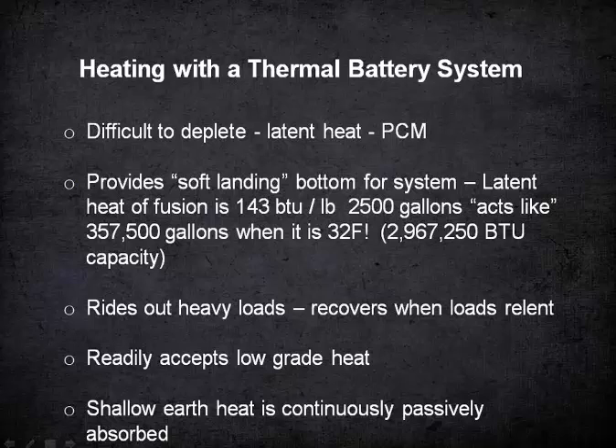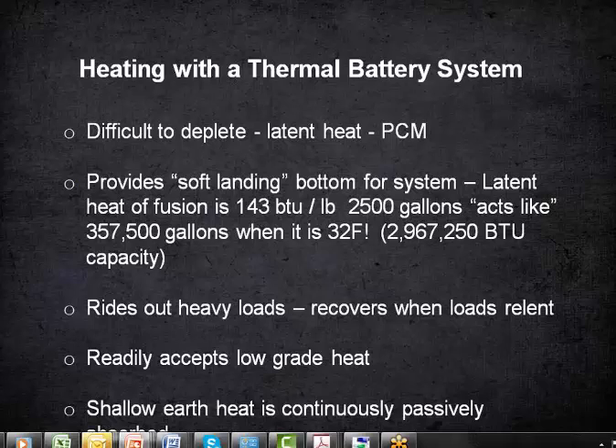The soft landing, as we call it, is the latent heat of fusion. It's 143 BTUs per pound. So 2,500 gallons is 20,750 pounds of water, which would be 20,750 BTUs per degree when it's liquid. But when it gets to 32 degrees, it's 143 times that 20,750 pounds of water, which means it starts acting like 357,500 gallons. Very difficult to deplete it.